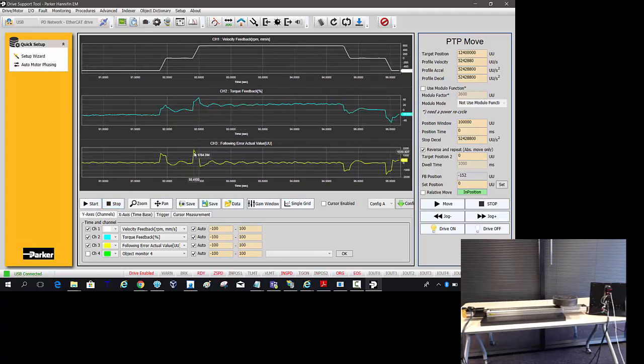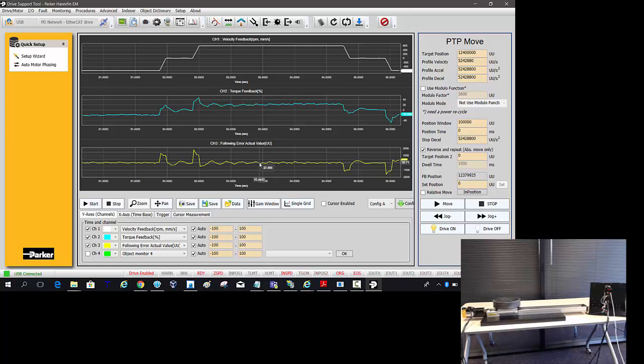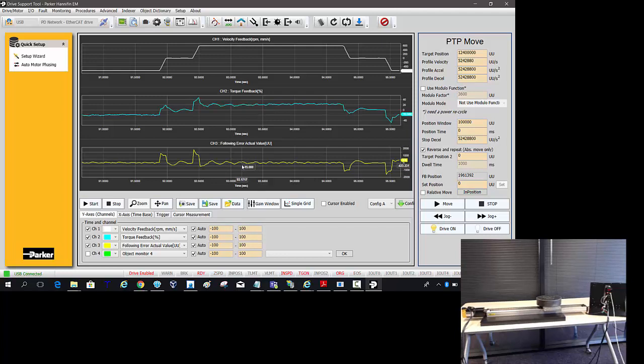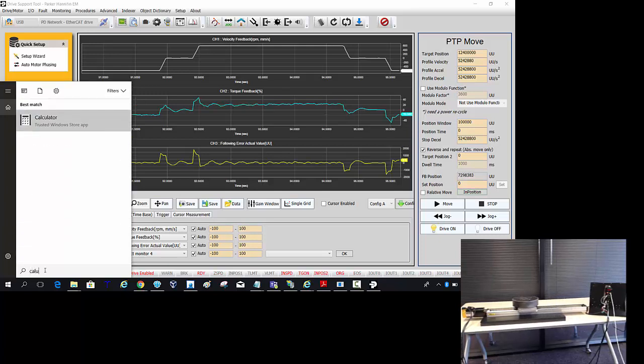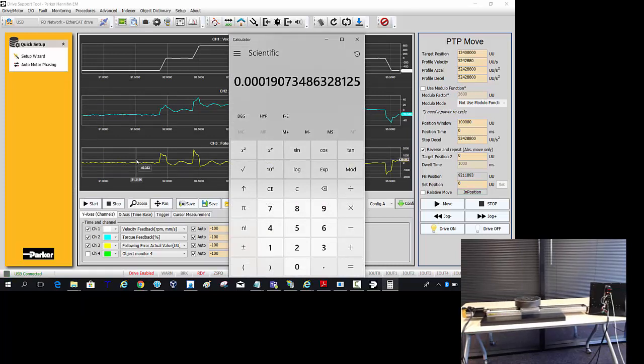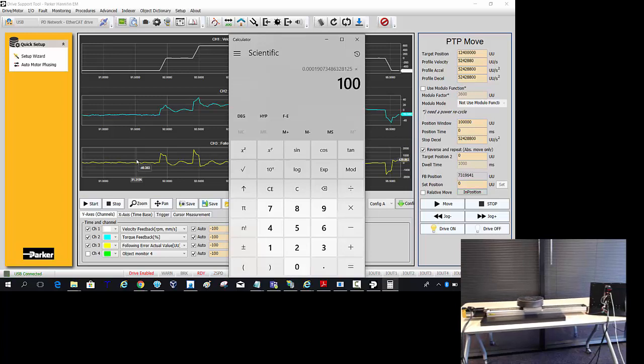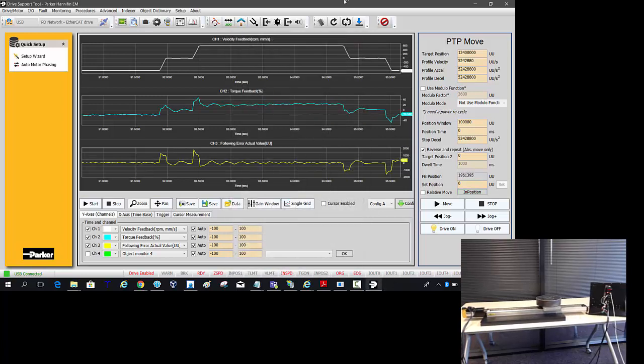Now you can see when we're moving, when we start to accelerate, there's only 1800 counts. And then it quickly settles into position within plus or minus 100 counts. And it's a 19-bit resolution. So 0.02 percent position error that we're settling in.